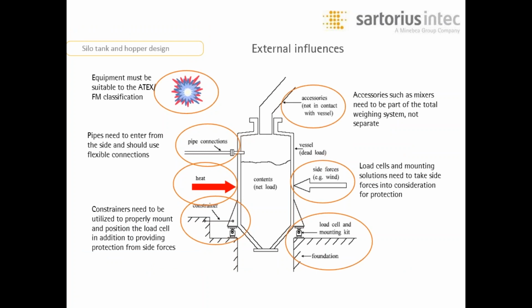If the load cell mounts do not have built-in constrainers or check rods, then they need to be added to the system in a manner that will restrict horizontal movement, but not the vertical. Side forces, like we discussed earlier, like wind and seismic matters, always need to be considered when designing a system. Most importantly, accessories, which are the most overlooked component, like mixers and other components, need to be added to the overall weight of the system and seriously taken into consideration when designing an accurate tank and vessel system.